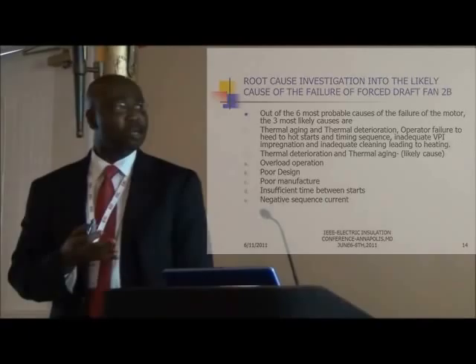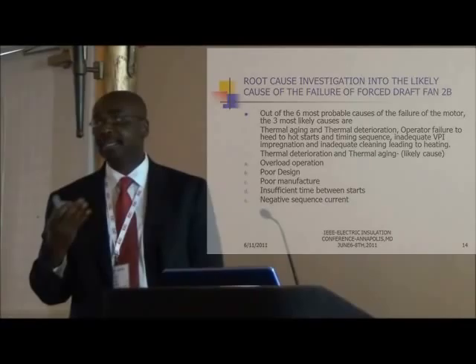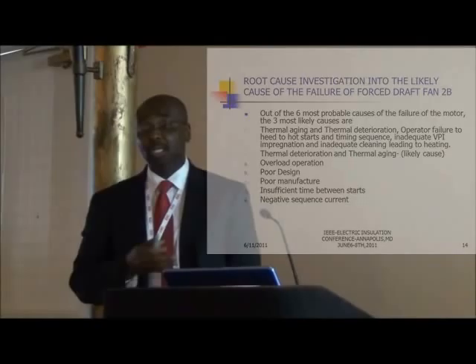Thermal aging can also occur due to overload. When you overload the motor, it can lead to gradual degradation of the insulation. Thermal deterioration can also occur due to poor design — for example, if a motor has blocked cooling ducts, it will lead to inadequate cooling, which causes degradation of the motor.